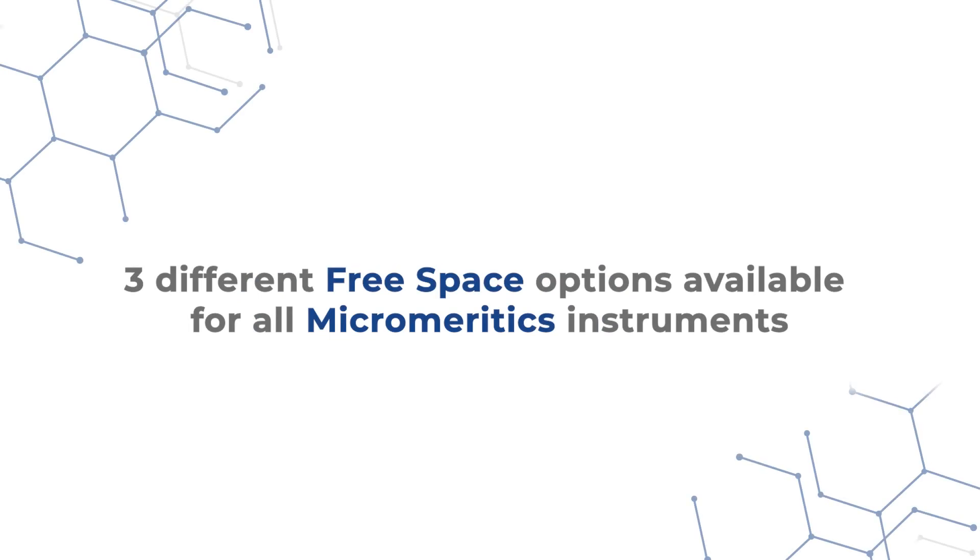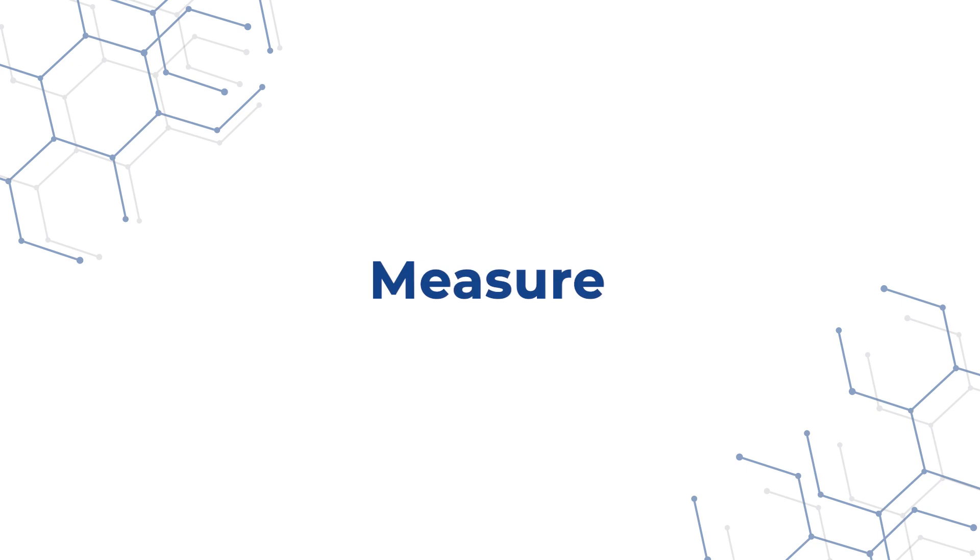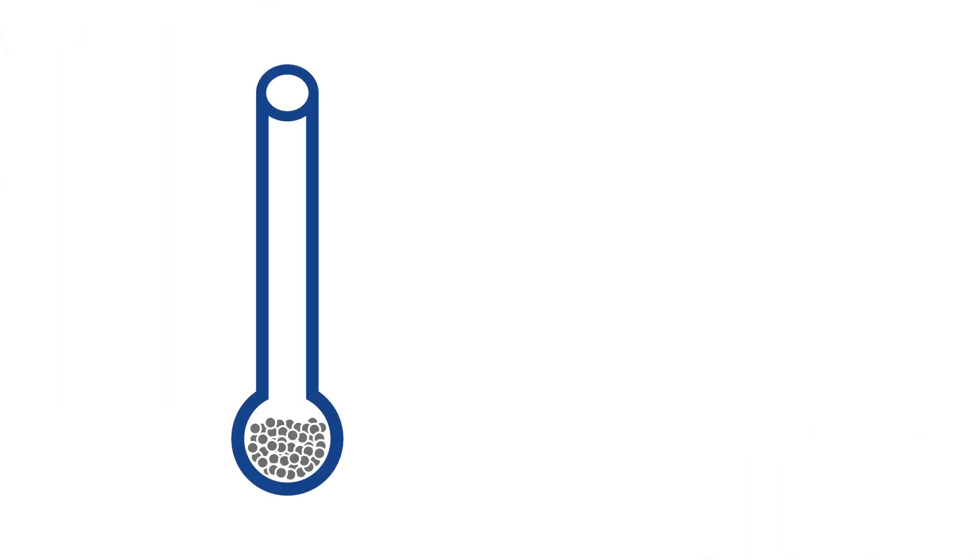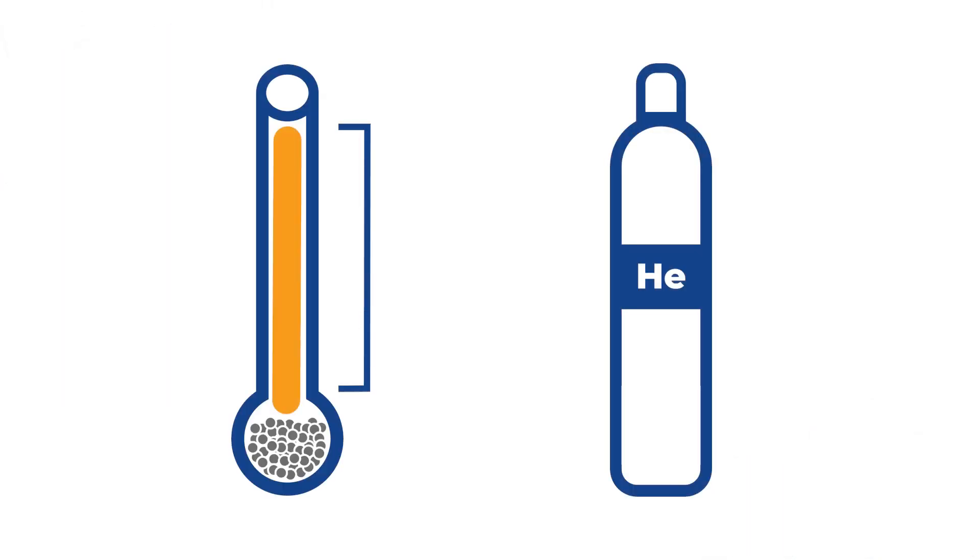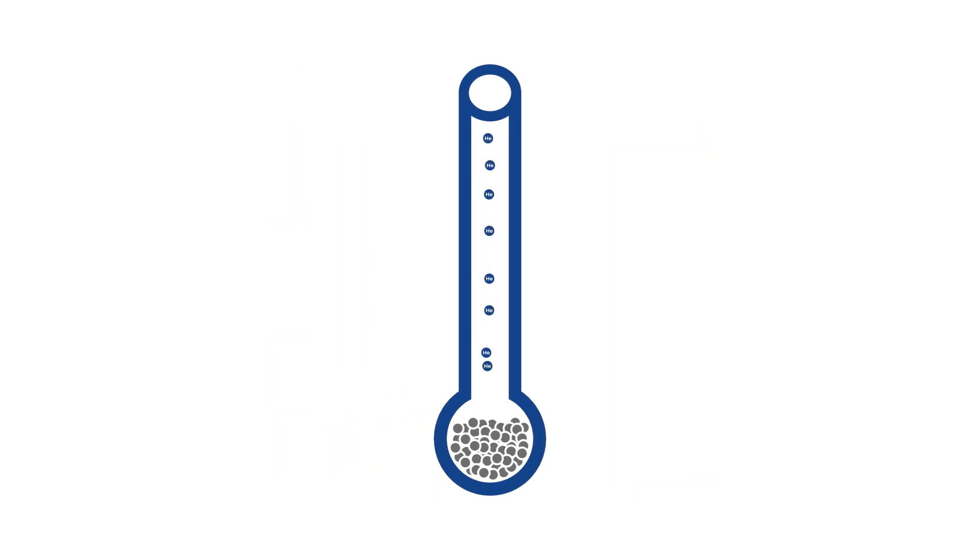There are three different free space options available for all Micromeritics instruments. The first one is measure. It measures the free space with helium before the analysis and gives the most accurate BET result. Helium is used to measure the free space due to its lack of interaction with most samples.